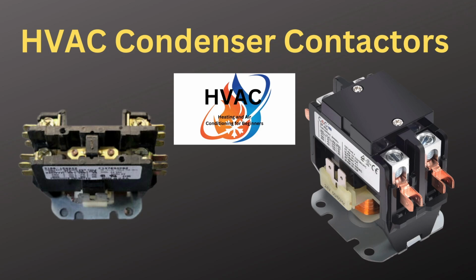Well, I hope that gets you a good understanding of what a contactor is. There's not a whole lot to it. All a contactor basically does is electrify, make magnetism, and pull the contactor in, which allows the high voltage, 208, 230, 220 volt as we call it, to circulate through the system and allows the condensing unit to operate. So with that, guys, I hope you understand a little bit about a contactor.